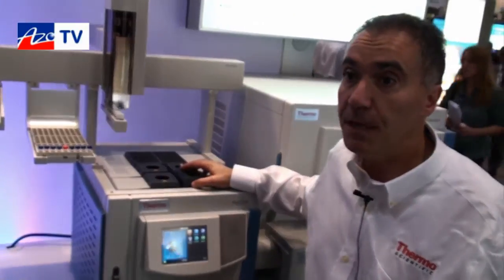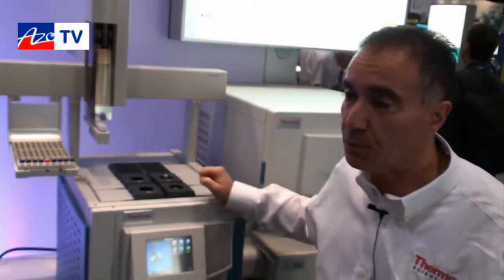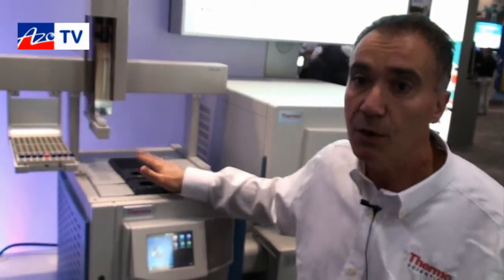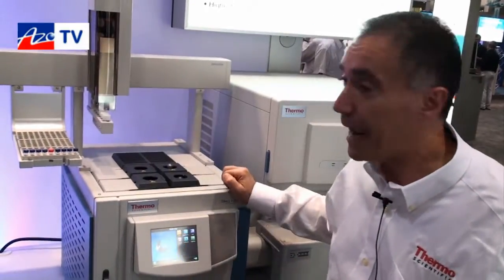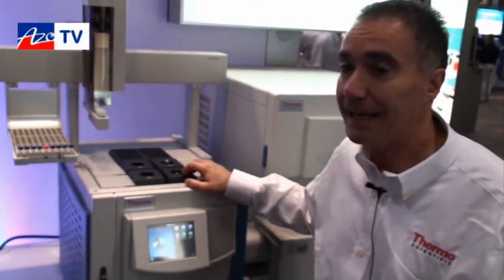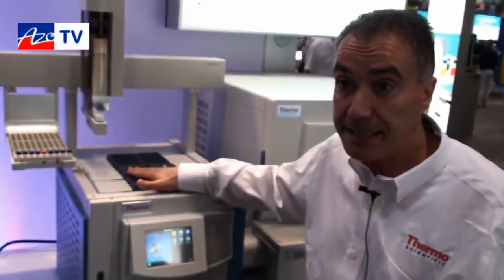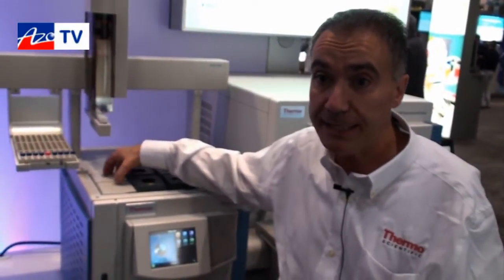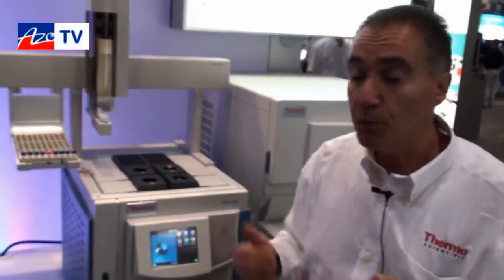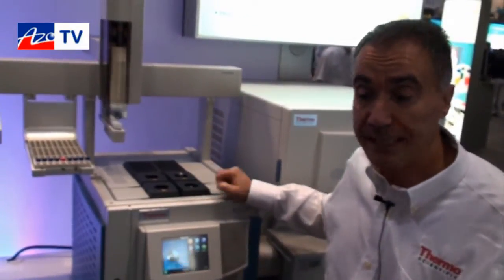Another way of improving productivity — for instance, for an environmental lab using this equipment for pesticide analysis with an electron capture detector — is that if you receive demand for samples to be analyzed with a nitrogen phosphorus detector for pesticides, you can at any time add a new NPD detector and be productive using this instrument for that kind of analysis.